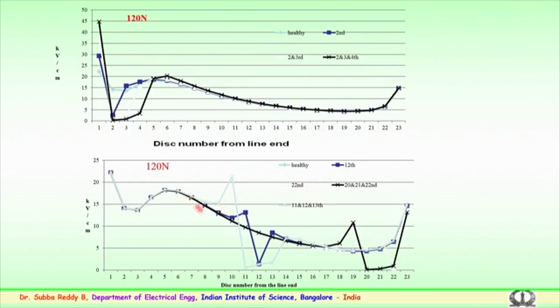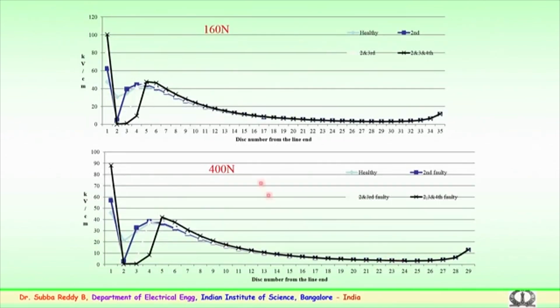Similarly, what happens in case there are failures in the middle of the string? You can notice that in case of the middle of the string, the field gets modified, but without much disturbance to the initial conditions. So, no major threat happens. Even if the fault conditions are somewhere here, in the last 20-25 near the ground end, there are no serious effects. A similar study was conducted for various insulators, 160 kilonewtons for a 765 kV line, that is 35 insulators in a series.